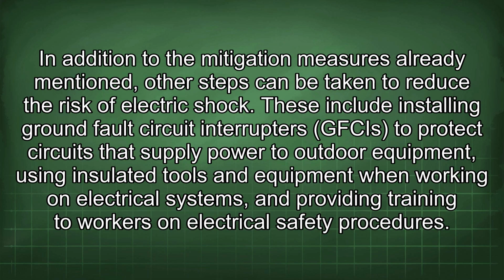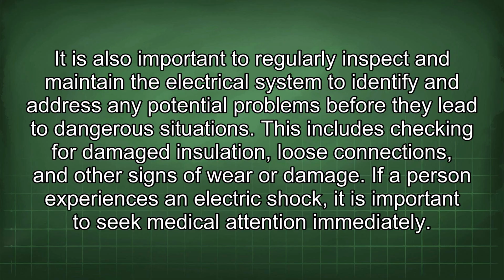In addition to the mitigation measures already mentioned, other steps can be taken to reduce the risk of electric shock. These include installing ground fault circuit interrupters (GFCIs) to protect circuits that supply power to outdoor equipment, using insulated tools and equipment when working on electrical systems, and providing training to workers on electrical safety procedures. It is also important to regularly inspect and maintain the electrical system to identify and address any potential problems before they lead to dangerous situations. This includes checking for damaged insulation, loose connections, and other signs of wear or damage.